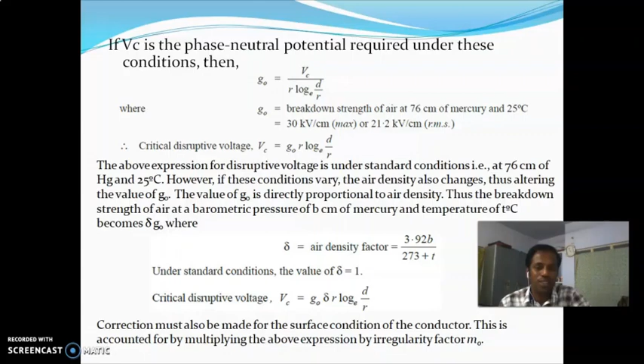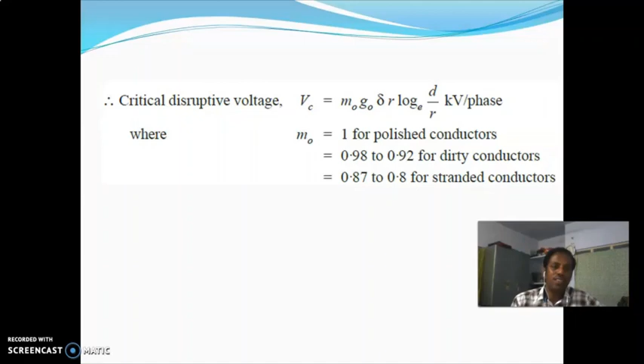And we know normally we are using stranded conductors. The stranded conductors have an irregular surface area. So it is affected by the irregularity factor m0. So the critical disruptive voltage is multiplied by the irregularity factor: m0 times G0 times delta times r log of d by r. The unit is kilovolt per phase. This m0 is given by the manufacturer of the conductors. The value is 1 for polished conductors, 0.98 to 0.92 for dirty conductors, 0.87 to 0.8 for stranded conductors. The dust is naturally formed under stormy conditions above the surface.